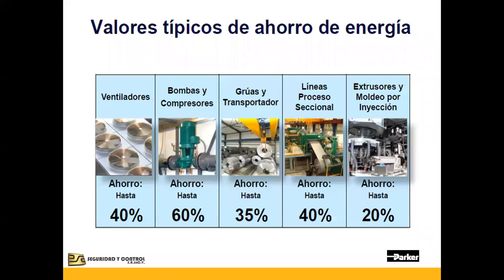Está demostrado que en ventiladores el ahorro puede ser hasta del 40% en cuanto al consumo eléctrico. Puede ser una buena inversión conectar los ventiladores o motores a un drive que genere ahorro en el tiempo. Para bombas y compresores está aún mejor: se habla de hasta el 60% de ahorro energético. También se puede conseguir ahorro en grúas, transportadores, líneas de proceso y en inyectores de moldeo.